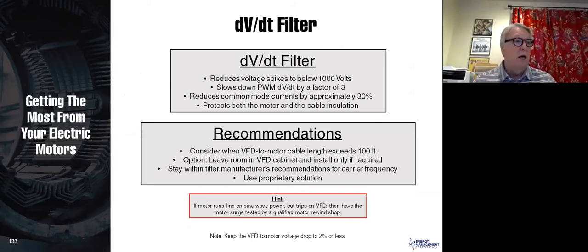So this is a little bit of a summary here. DVDT filters reduce voltage spikes below 1,000 volts. They slow down the PWM DVDT by a factor of 3. They reduce your common mode currents, which we'll talk about in a moment, by approximately 30%. And they protect both the motor and the cable insulation. So you can consider using that whenever your cable length exceeds 100 feet. Different manufacturers have different numbers for that. It just depends on how conservative they want to be. 100 feet is what I've chosen. Some manufacturers will say 70 feet, or some will go 125 feet. But I think 100 feet is not a bad rule of thumb.